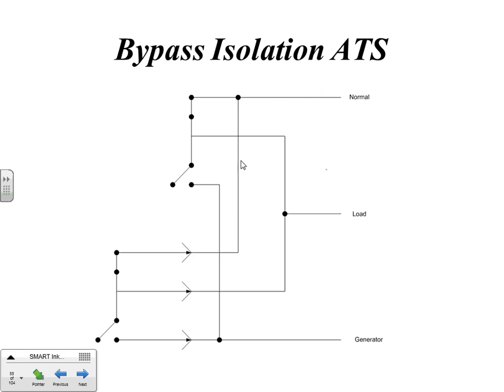This is the automatic switch down here. Notice that I've shown a contactor here, and it can be removed. It can be racked out. That will allow, in an emergency, using the emergency system to finish an operation that's in progress, always keeping load supplied to where it's needed, the most critical.